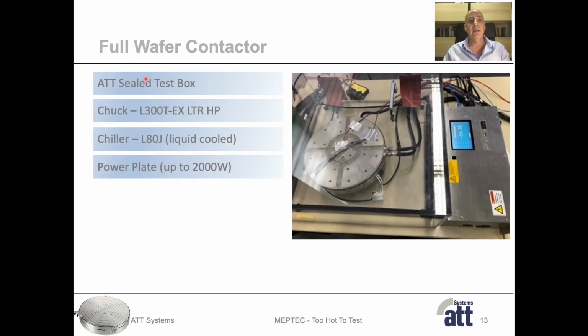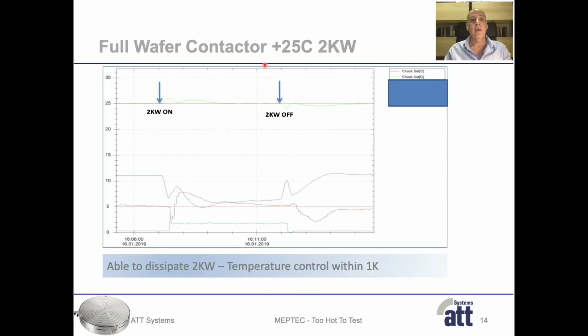So this slide shows the test setup for the full wafer contactor tests. We use the sealed test box, our 300mm LTR chuck with 9 sensors, our L80J liquid cooled chiller, and a multi-range power plate with up to 2000 watt, which was put on top of the chuck system to simulate the full wafer contact touchdown. The first graph shows the test results at plus 25 degrees C. The red line here is the chuck set temperature, and the green line reflects the actual chuck temperature.